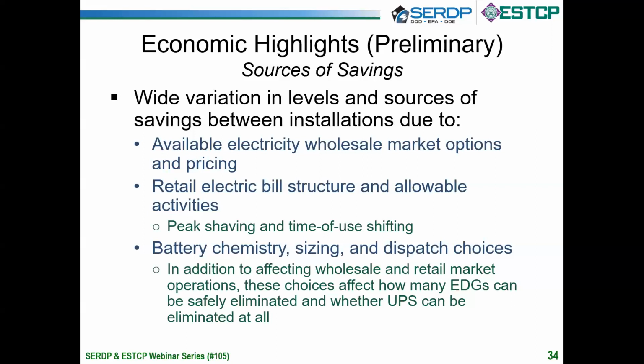There are also factors related to the batteries selected that drive the economic results. For example, lithium-ion chemistry batteries tended to outperform other chemistries, especially when paired with fast-responding equipment and controls, such as ultracapacitors and phasor-based controls. Contractor choices of how they configured and operated the batteries mattered as well. Lithium-ion batteries with a high-speed companion tended to be a way to reduce the number of UPS needed.